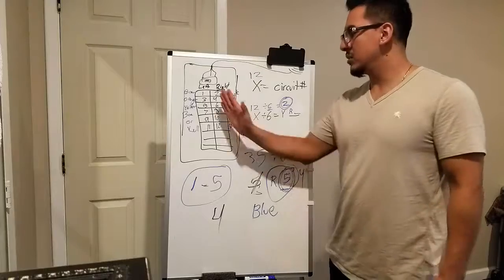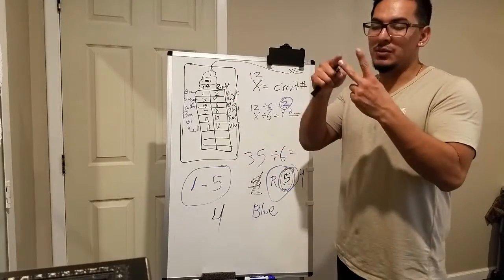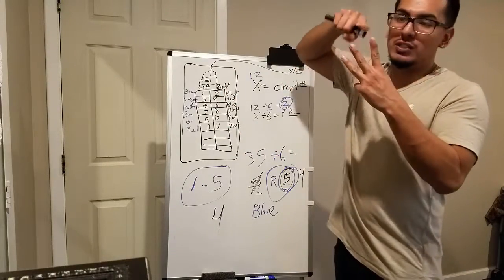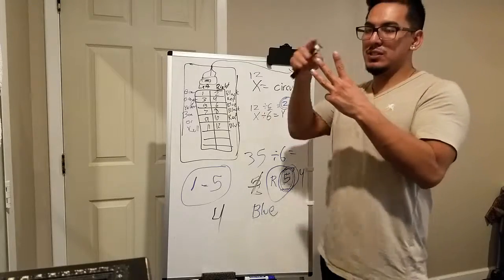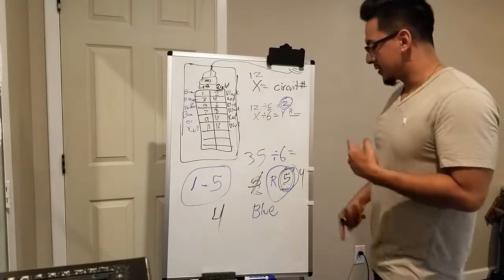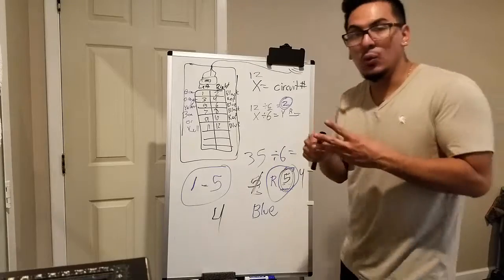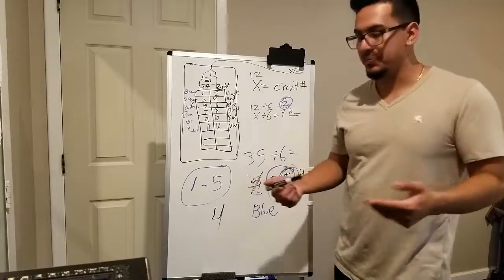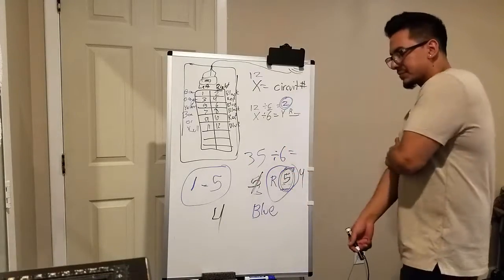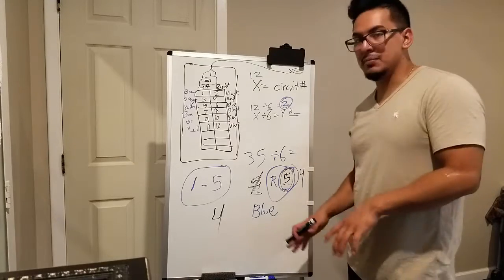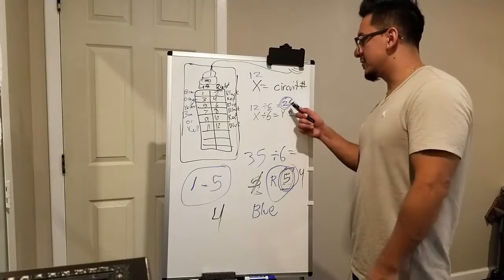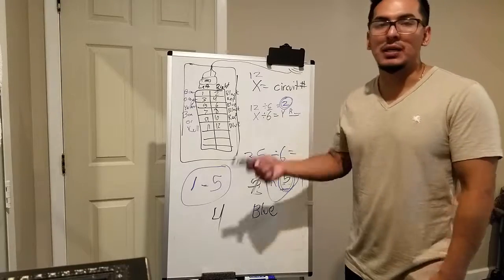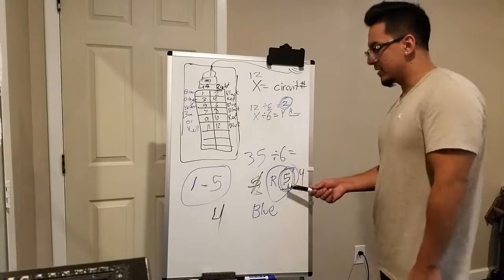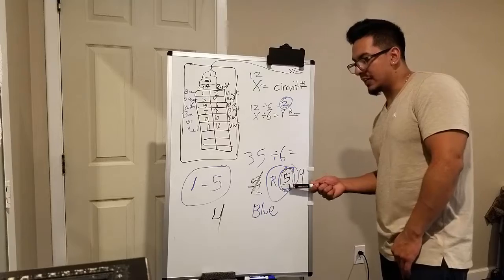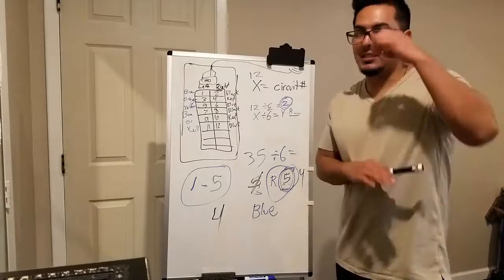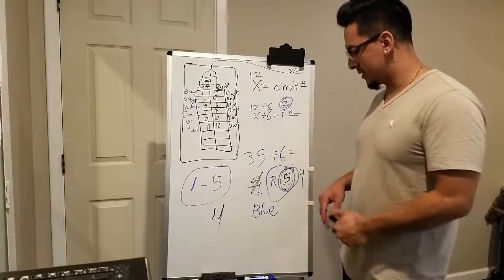The remaining number is 5, and you go back -- 5 is an odd number, so you count 1, 3, 5. If it's low voltage, that's black, red, blue, or if it's high voltage, brown, orange, yellow. So 5 would be blue or yellow. It doesn't matter whether it's a whole number or a remainder of 5 -- both give you yellow or blue, and they're both right.